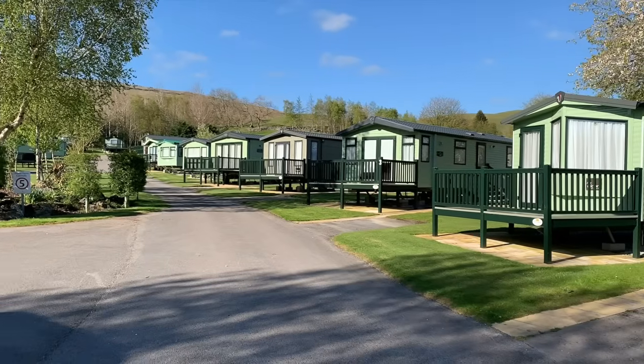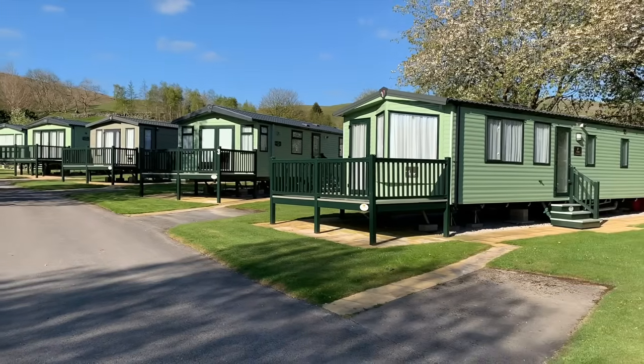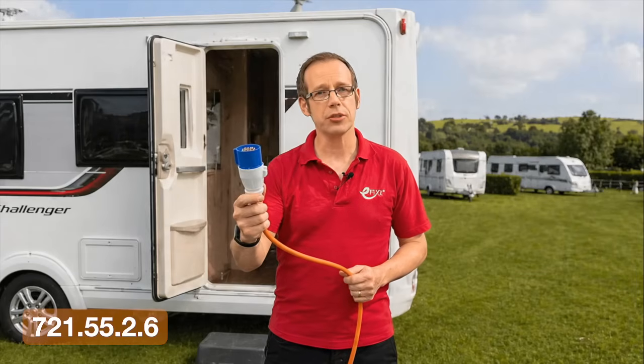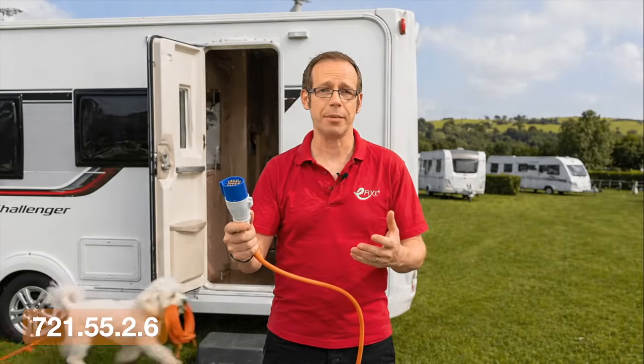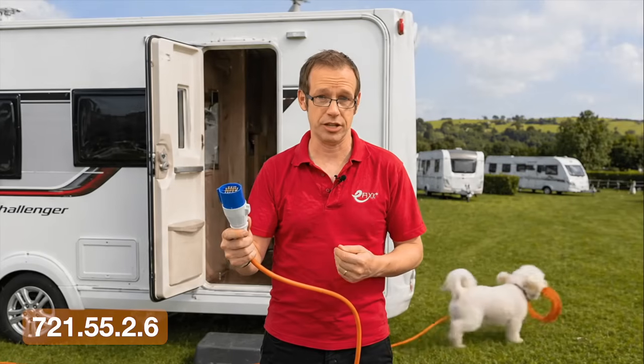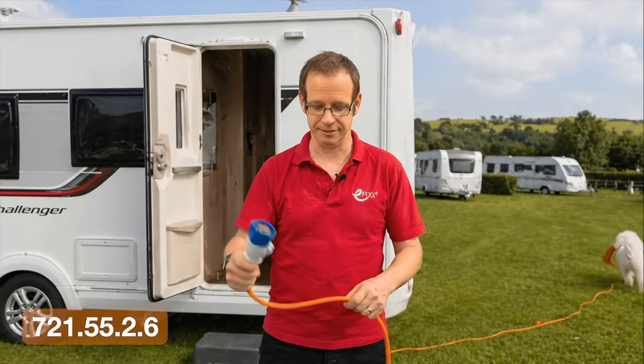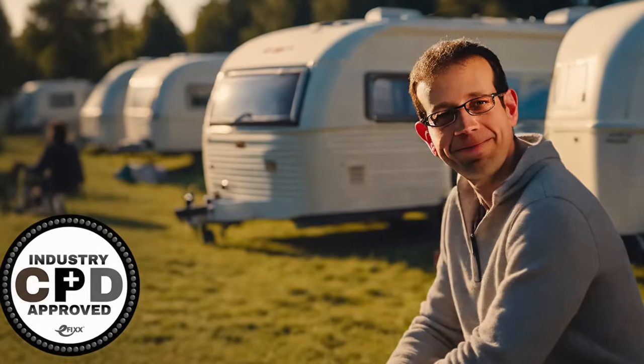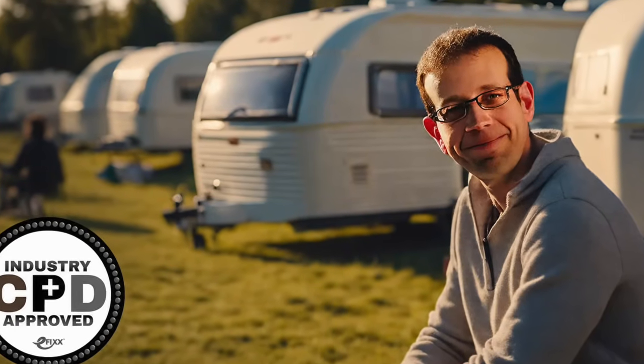There is also a practical requirement around caravan supplies. Regulation 721.55.2.6 now states that caravans must be supplied with a flexible cable that is at least 25 meters in length, with a minimum conductor size of 2.5 millimeters squared, and it should be colored orange. If you want to dive deeper into caravan installations and how they are set up in practice, Joe Robinson has done a full CPD on that, and I've left links in the description.